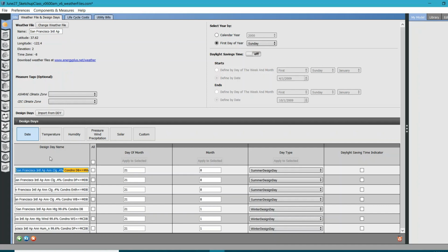Okay, so I have all the information for space types, I have geometry, I have the weather file now. And if you remember, I actually installed an ideal air load system for my HVAC information. All right, so we are good to run the simulation. When we run the simulation, we'll be able to get the information for internal loads, the space loads, something that Trace actually does, all the load calculations for you. Even OpenStudio can do it for you. You just need to provide some ideal air load systems, internal loads, envelope, and that's it.